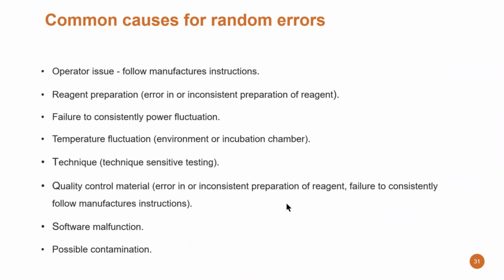Failure to consistently control power fluctuation of your instrument, temperature fluctuation, either in the environment or the incubation chamber of the instrument. The technique: you might have a very sensitive technique for your testing. Quality control material, yes, also the quality control material may have issues, for example, if you are not preparing them well. So my recommendation is to use fluid, ready to use quality control material to avoid any dilution or problems in the reconstitution of your QC material. There might also be software malfunction and also contamination.